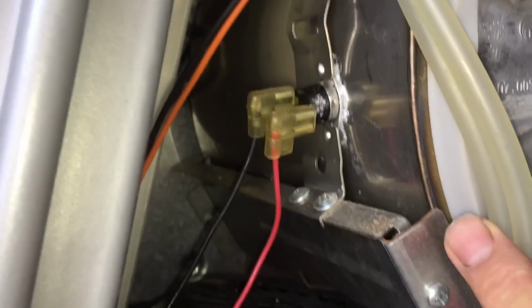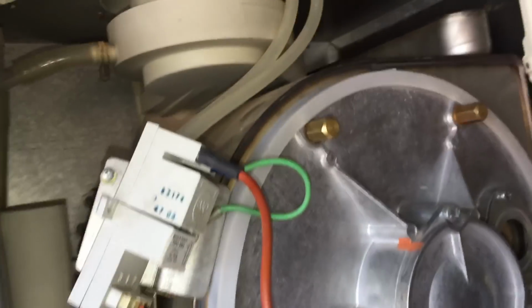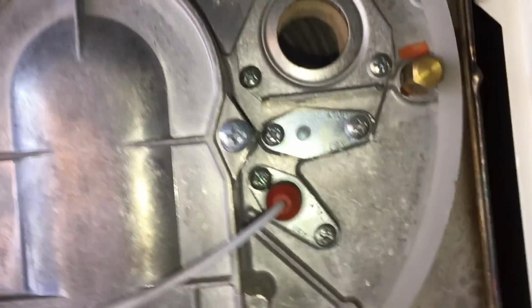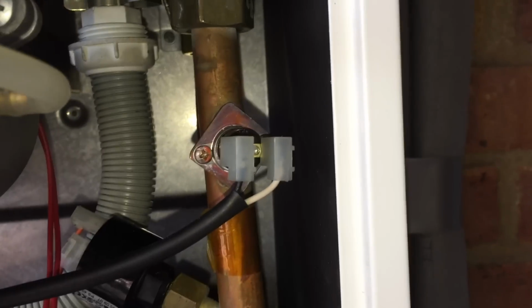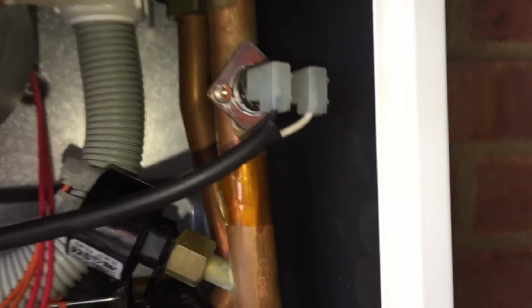It's got some form of overheat on there, a spark generator which is hanging off. We've got a spark electrode, an ionisation electrode for flame sensing, a nice big sight glass so we can have a look through when it's up and running. We have a water pressure sensor there, and an NTC there potentially, or an overheat. Let's have a look if we can find any NTCs in here.